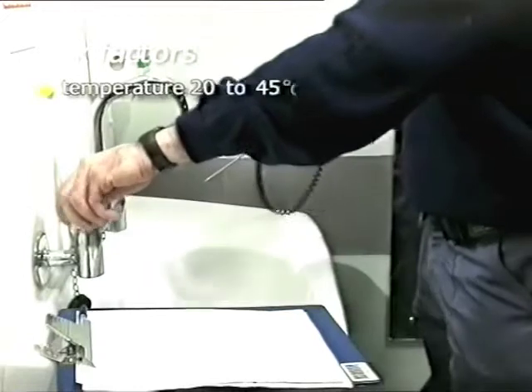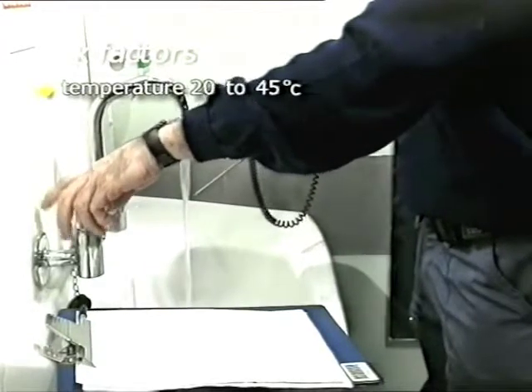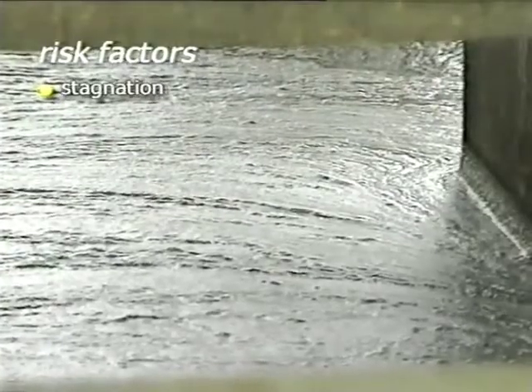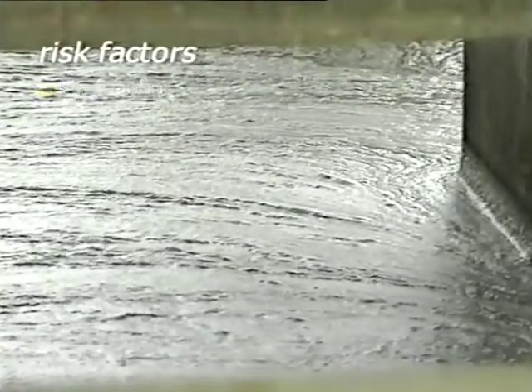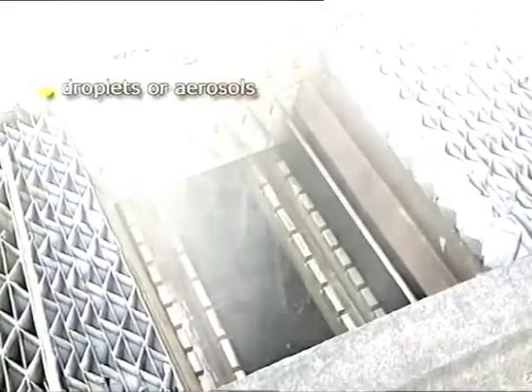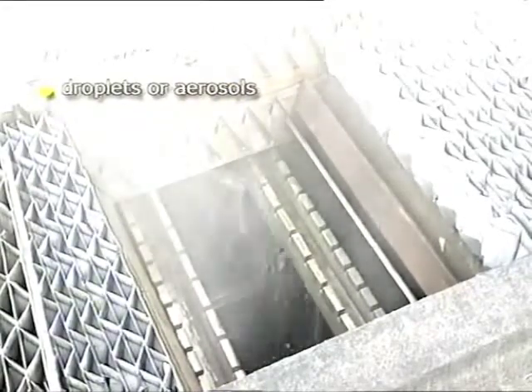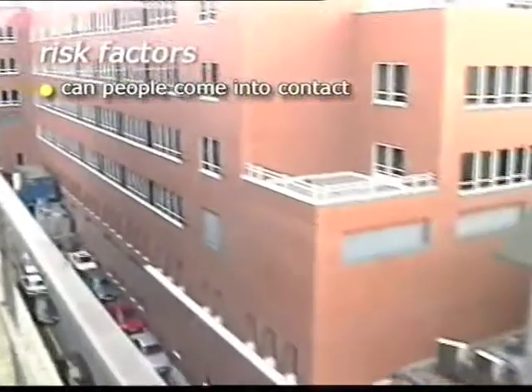The first thing that you need to do is to look at your workplace and ask yourself if there are conditions which would allow Legionella to grow and multiply. For example, is the water temperature between 20 and 45 degrees centigrade? Is there a source of nutrients? Are there areas where water can stagnate? Can your water system produce water droplets or aerosols which will spread over a wide area? And can people come into contact with these droplets or aerosols and inhale them?